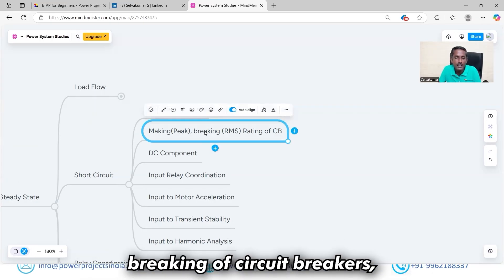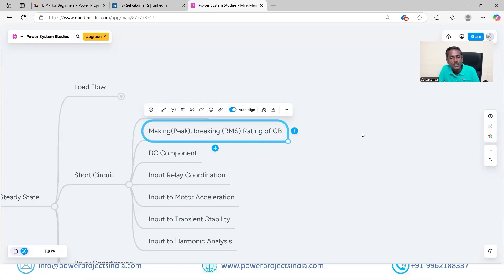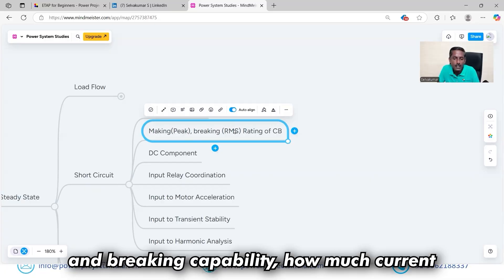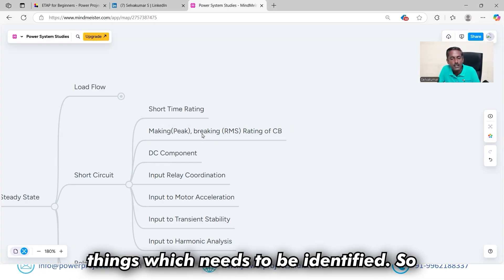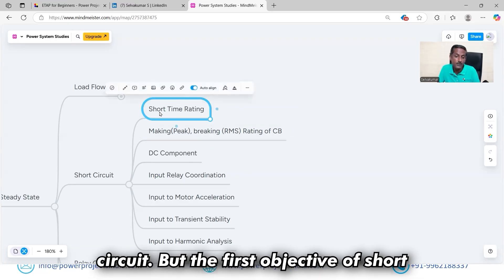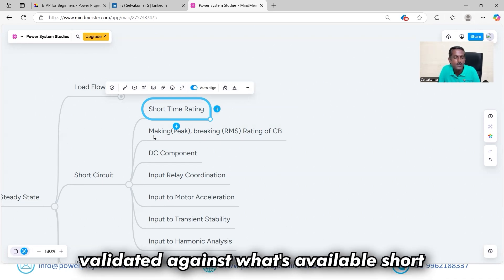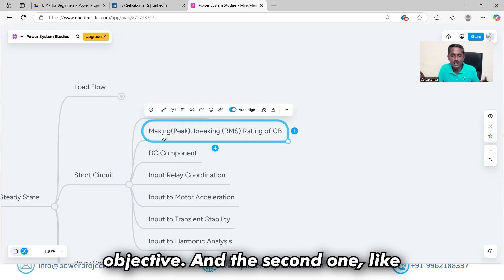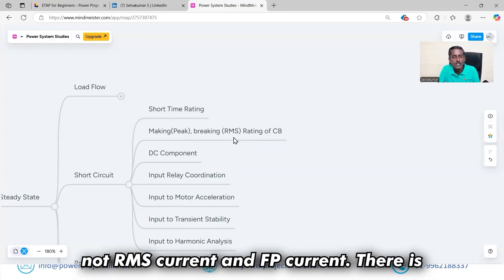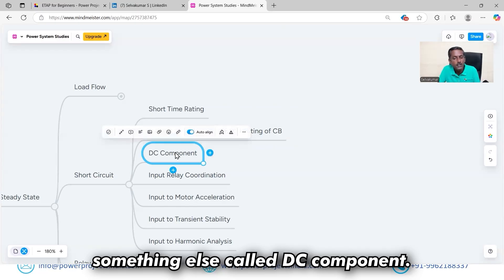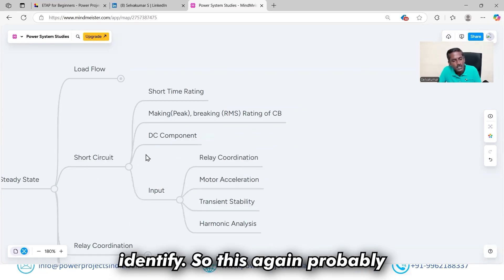You also need to find out the making and breaking capability of circuit breakers — the making peak current and the breaking RMS current. Circuit breakers have a making capability and a breaking capability: how much current it can safely interrupt and how much it can safely make. Beyond RMS current and peak current, there is also a DC component, and the breaker has a capability of interrupting DC current, which also needs to be identified.